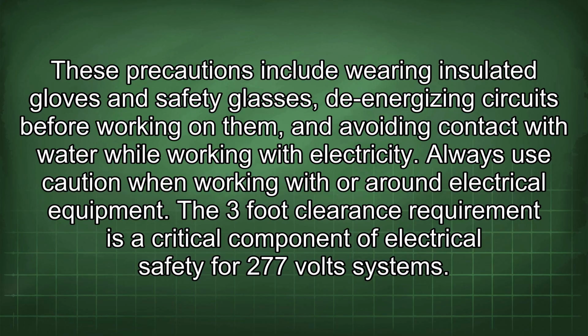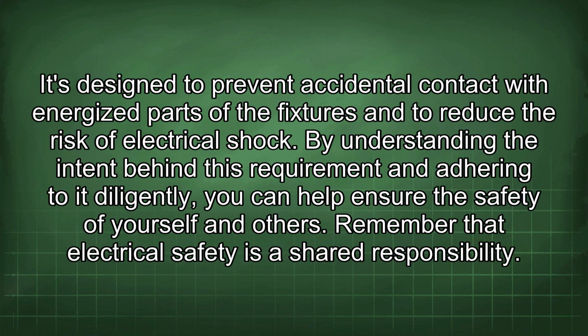The 3-foot clearance requirement is a critical component of electrical safety for 277-volt systems. It's designed to prevent accidental contact with energized parts of the fixtures and to reduce the risk of electrical shock. By understanding the intent behind this requirement and adhering to it diligently, you can help ensure the safety of yourself and others.